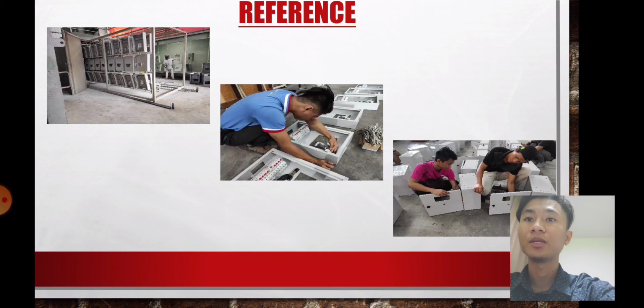After installing the main switch, all RCCBs are installed on the distribution board and arranged according to the sensitivity rate, with the trip button. Okay, then cut the bus bar plate for the neutral terminal and the earthing terminal, as well as arrange all the bus bar plates on each distribution board. After finishing cutting the bus bar plate and stacking it, then cut and make 4 mm cable fitting on the main switch. After finishing the fitting on the main switch, make fitting for MCB for the lighting circuit and power circuit. For the lighting circuit, we are using 6 ampere and for the power circuit 20 ampere. Both of the circuits are using 4 MCB.